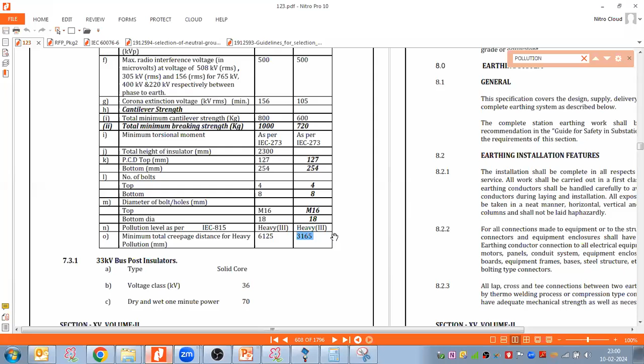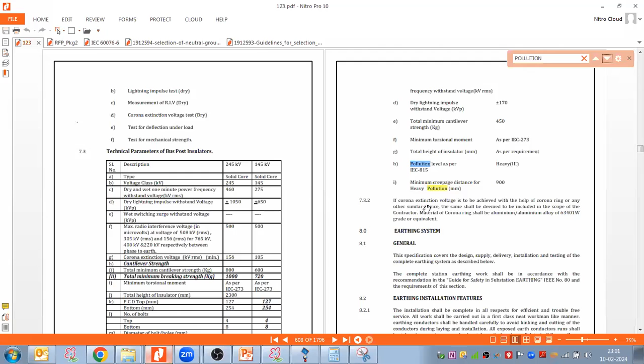Minimum total creepage distance for heavy pollution. So they have given the phase-to-phase distance, taking heavy pollution into account. As I told you, you require the pollution level data. Could you see here, they have mentioned the pollution level, which is heavy, as per IEC 60815, heavy class 3 pollution. So you should check what the pollution level is in your case - it is heavy pollution, a polluted area.